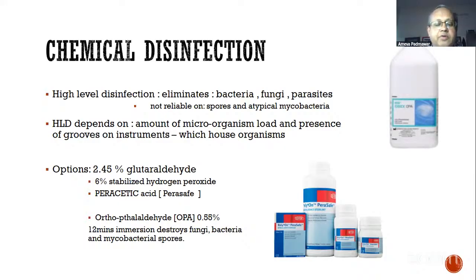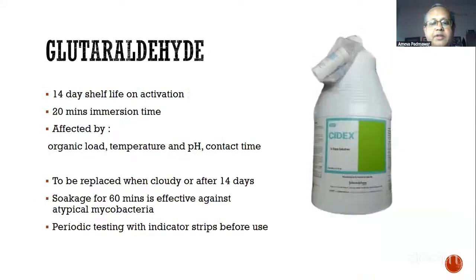Orthophthalaldehyde gets rid of all the mycobacteria in 12 minutes. So roughly, if you are going to use any of these immersive solutions, you have to dip your instrument for a period of roughly 20 minutes. Okay. So this is the glutaraldehyde canister for one set of, when you're using the type of steel tray, which I showed you in my CSSD department, we have to use at least 5 liters so that all the instruments are appropriately immersed. The instrument has to be submerged under the upper meniscus of the fluid.